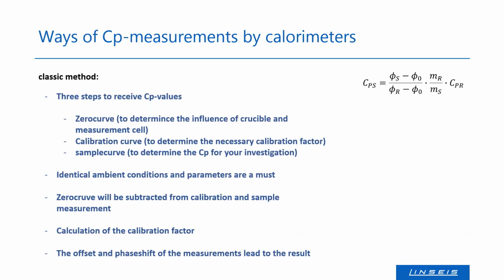The classic method is, I think, the oldest and the easiest way to measure CP with DSCs. Basically, we need 3 steps to receive the CP results. At first, we need the zero curve. This is just the crucible in the measurement system without any sample or reference material. It gives us information about the measurement system itself. Under the same conditions, we then measure the calibration. We have to determine the calibration factor for the CP measurement, so we need to heat up a reference and calibration material, for example sapphire. And last but not least, of course, is the sample measurement, because we want to determine the CP for our investigation.